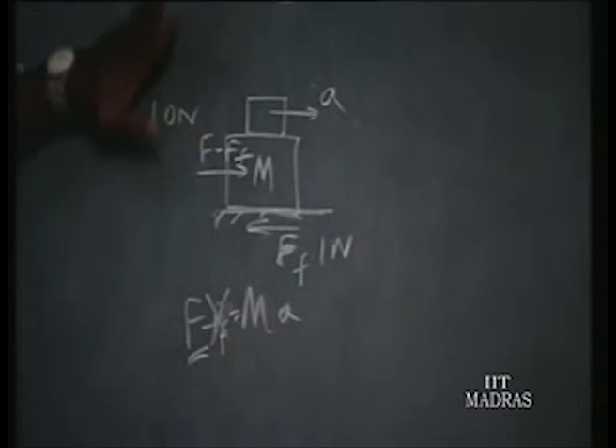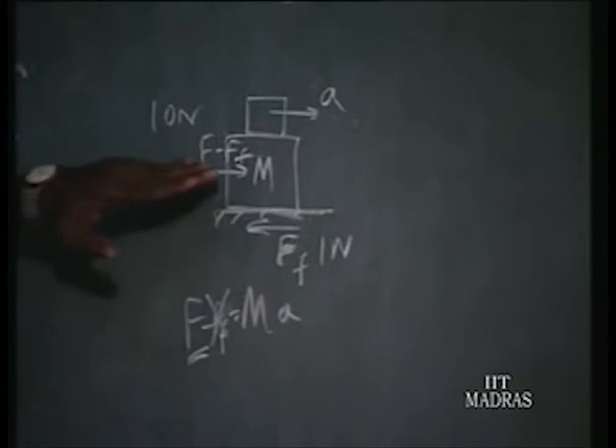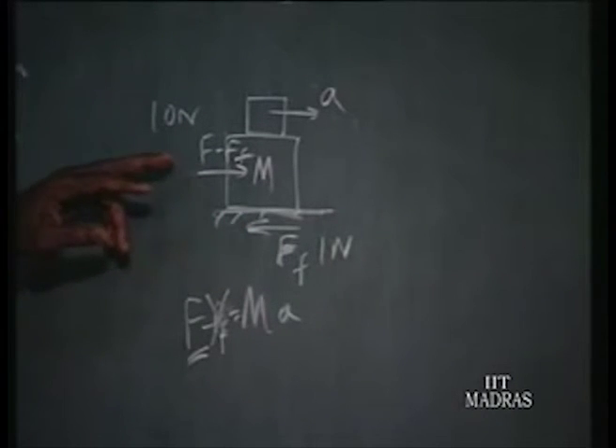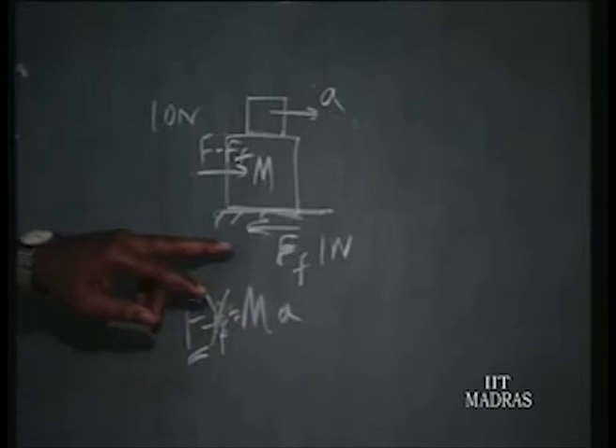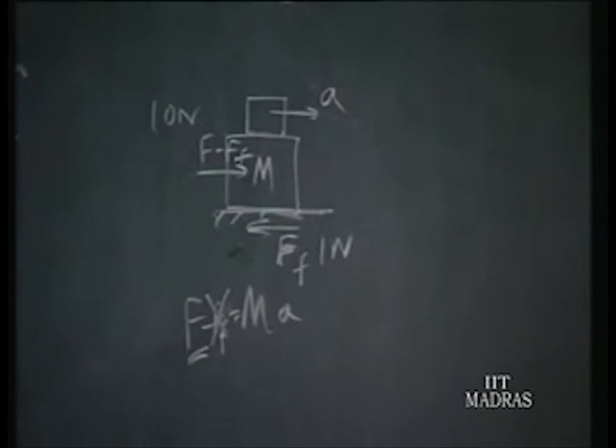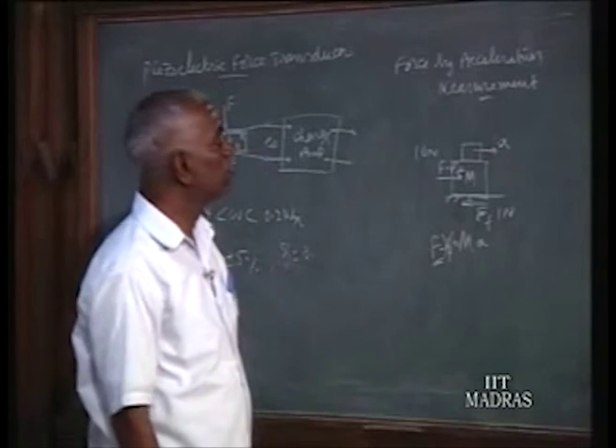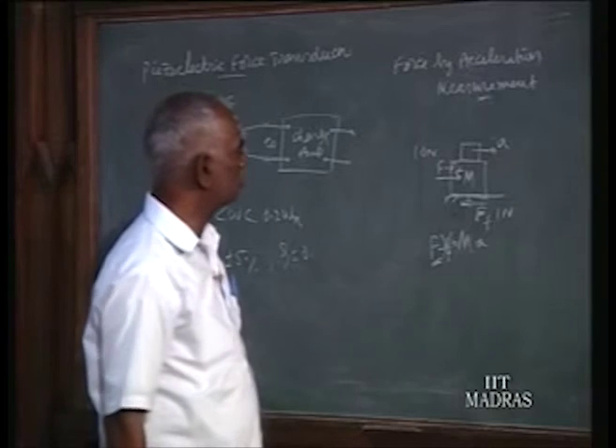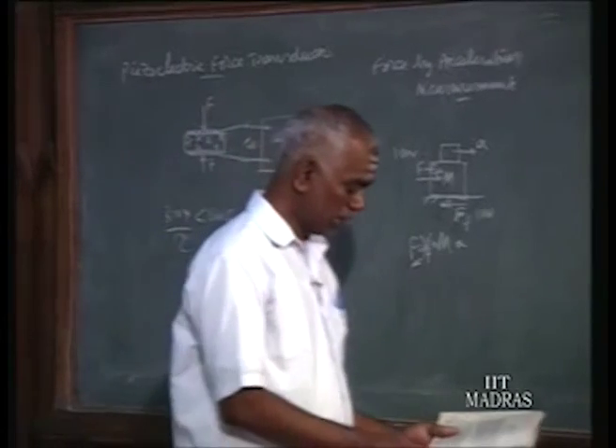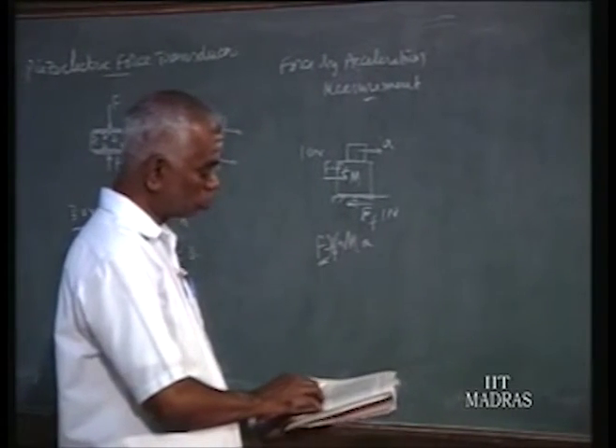So this instrumentation you can use only when the resultant force is the only force, or if there is another force, that force amount should be known to avoid the error in the measurements. The drawback is that the acceleration is a result of the resultant force. That is the point you have to note. The next instrument we are going to discuss is a closed loop instrument.